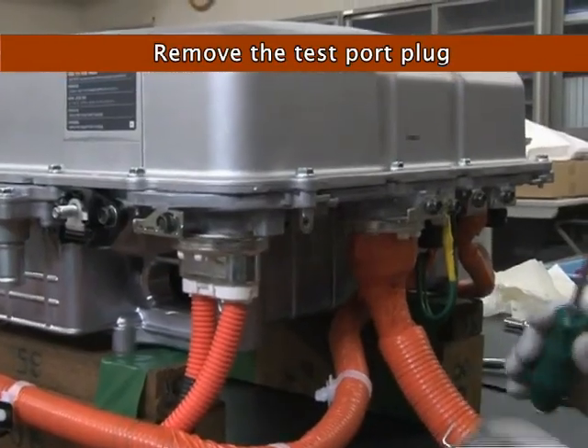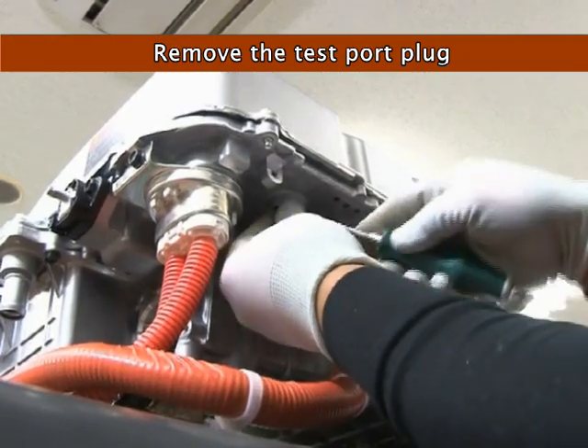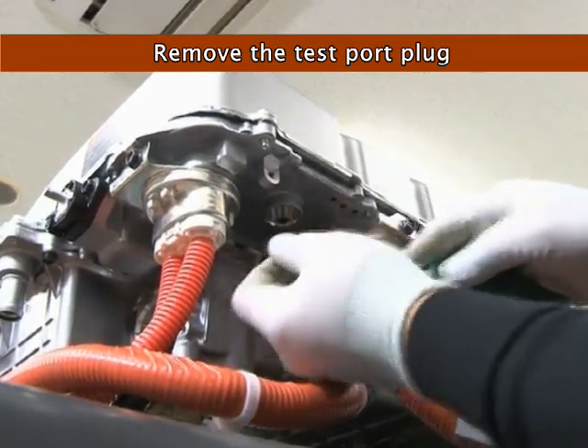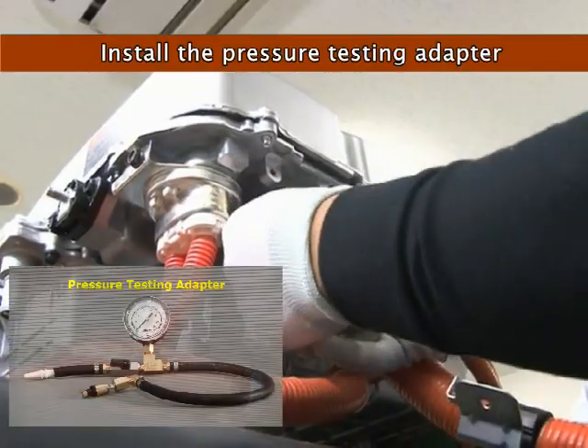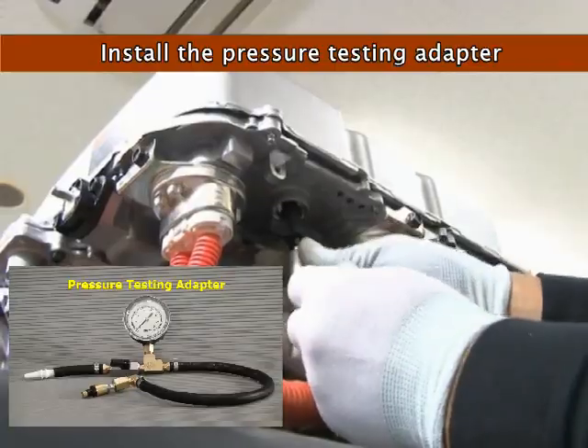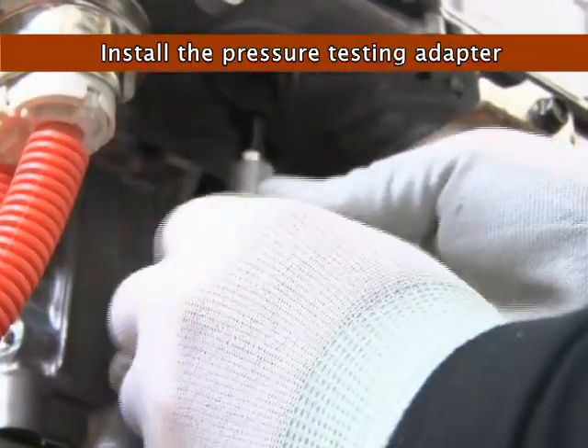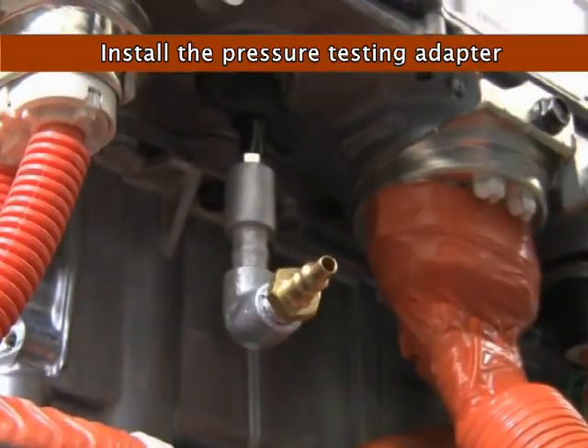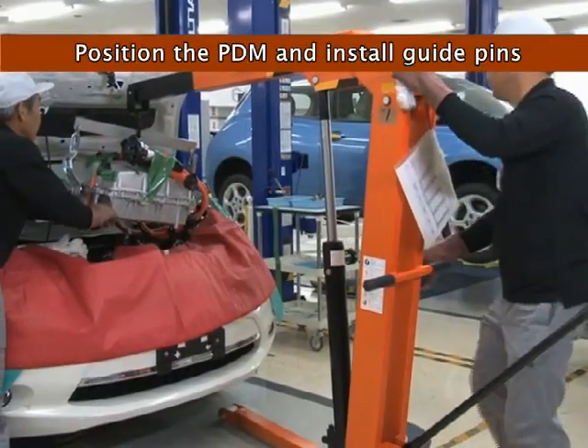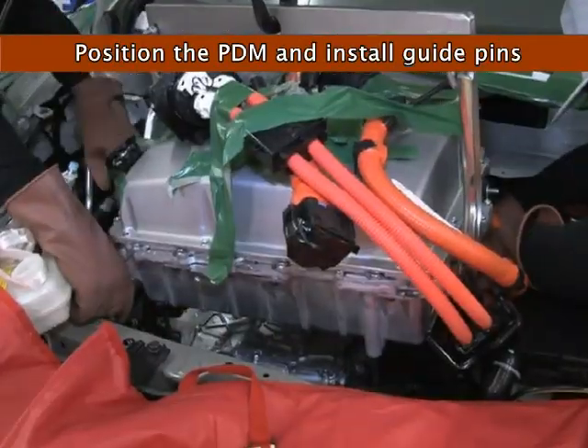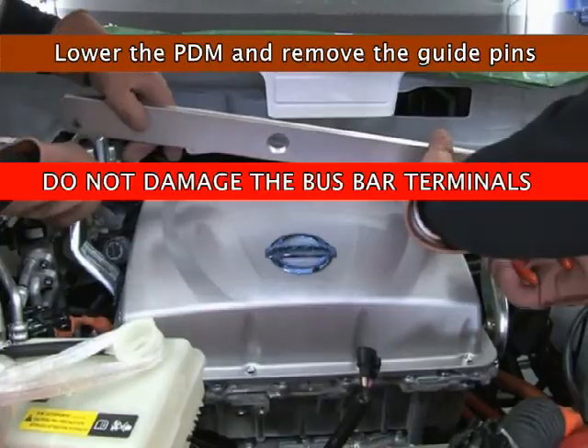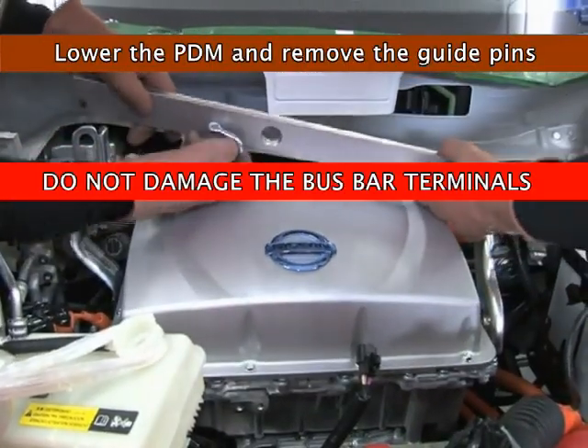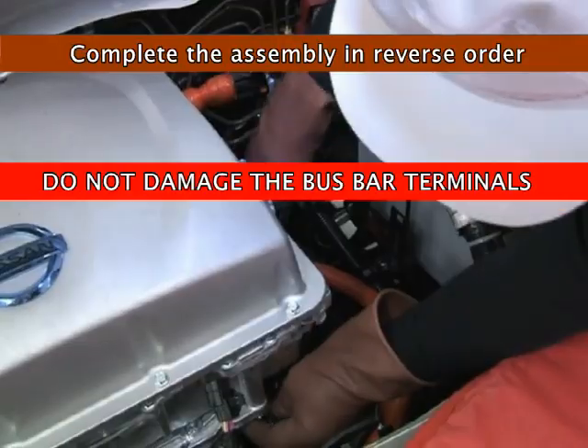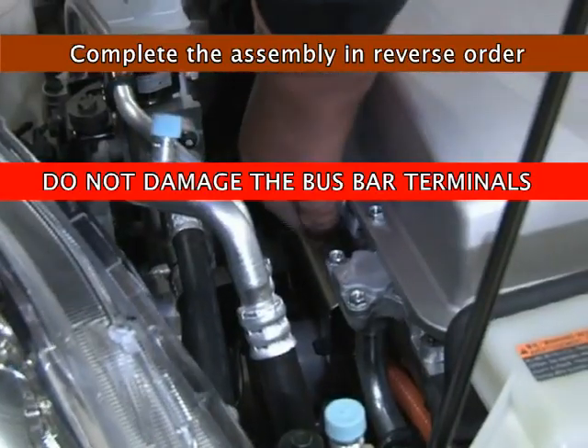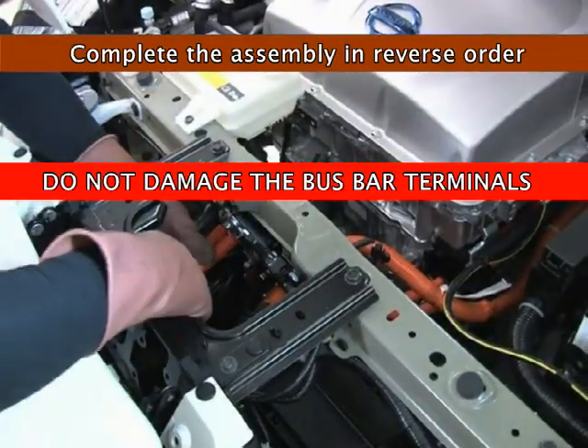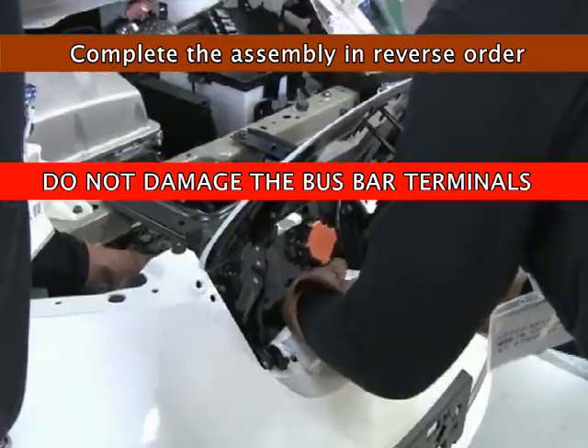Before installing the PDM, remove the plug at the back of the PDM housing. Install the pressure testing adapter into the test port. Position the PDM over the inverter and install the guide pins in the appropriate locations. Carefully lower the PDM into place on the inverter. Remove the guide pins and complete the installation in reverse order of disassembly. Take extra care not to damage the bus bar terminals to the inverter.